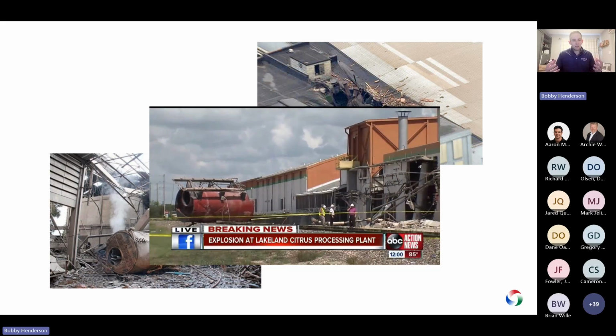We sell fire tube boilers, so I'm not here to condemn the design necessarily, but one great feature of a water tube or a smaller once through water tube design like Miura is you just don't have the explosive potential that you do with a traditional fire tube boiler with a large volume of water. I'll show you here in a moment what the insides of this boiler look like. But as we shrink that volume of water down, we really lose that explosive power that might happen in case of operator error, safety failure. Usually these are when everything goes wrong, including operator error, including mechanical error and lack of maintenance. But if we were to have a catastrophic pressure vessel failure with a Miura boiler, that explosion would stay inside, that pressure vessel breach would stay inside of the jacketing.